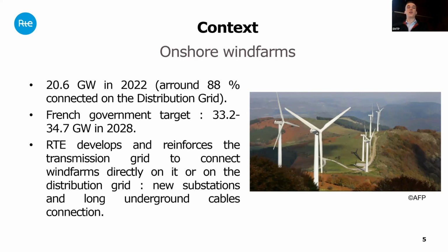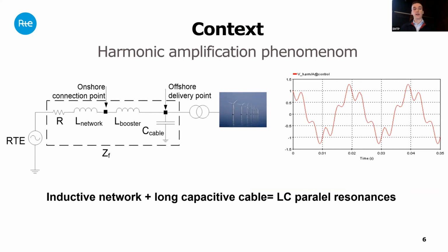At RTE, we develop and reinforce our transmission grid to connect wind farms directly on it or on the distribution grid. We need to connect new substations, which can be linked by long underground cables. As you may know, our network is mainly inductive because of the majority of overhead lines and because the machines are mostly inductive.